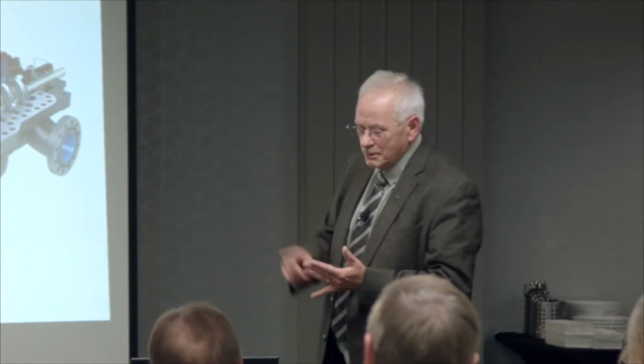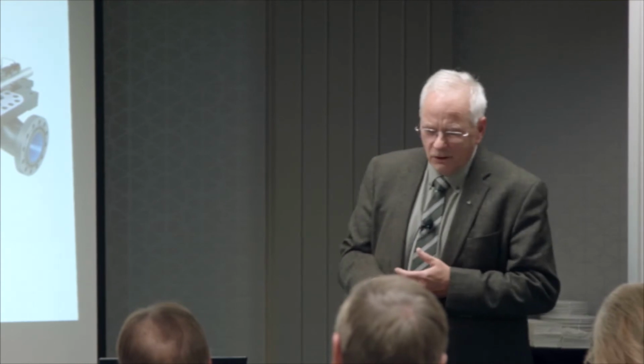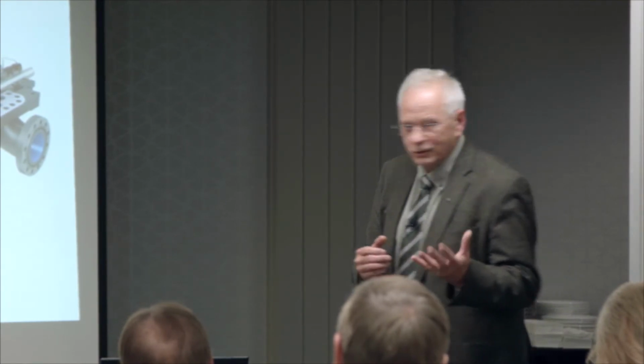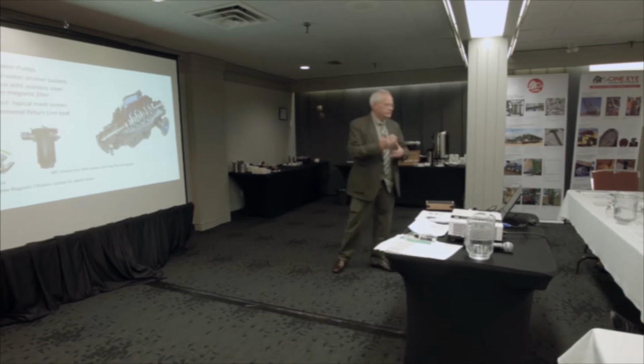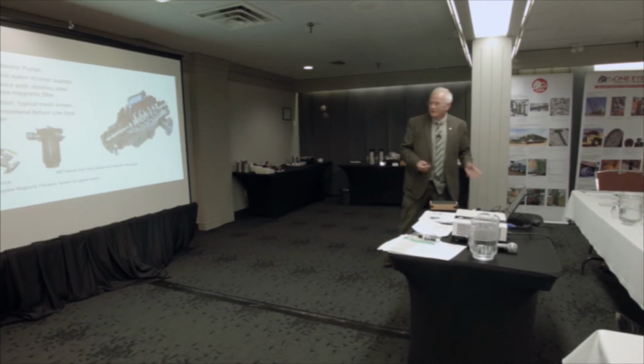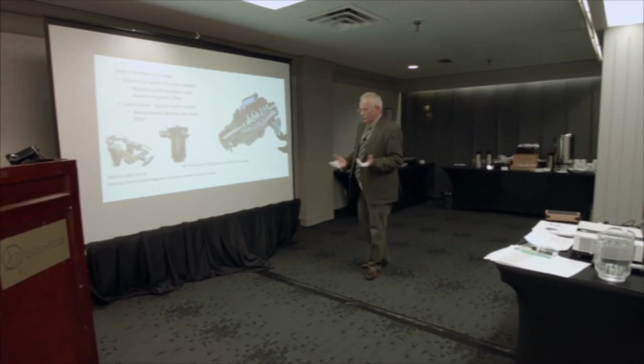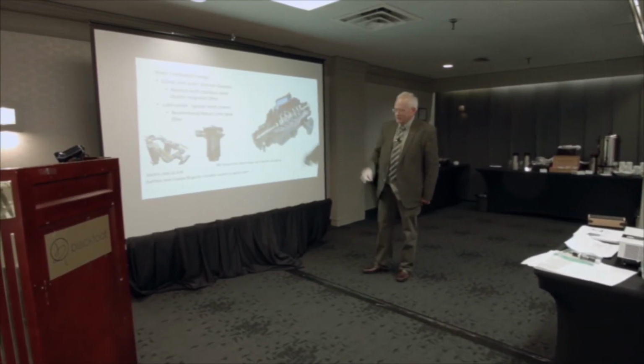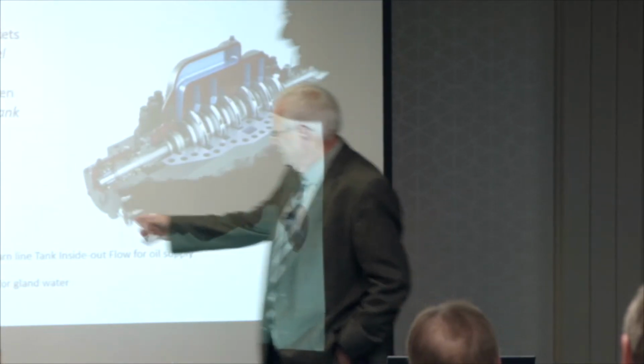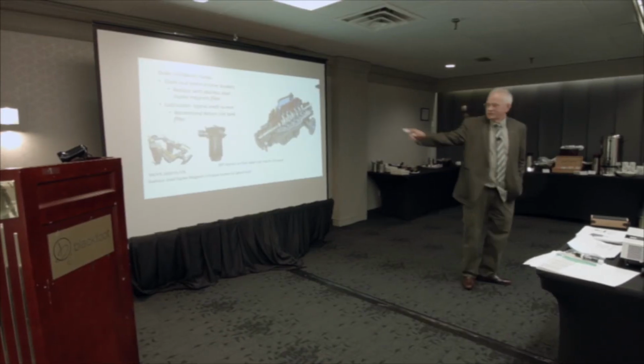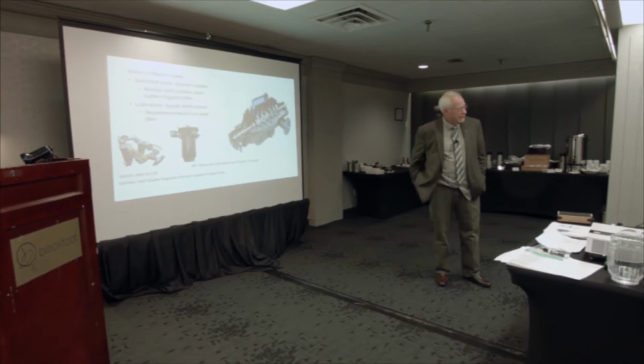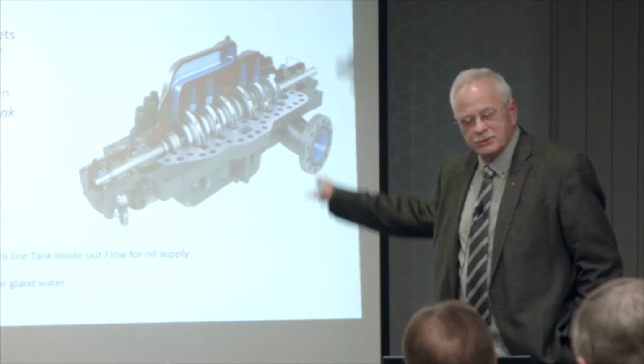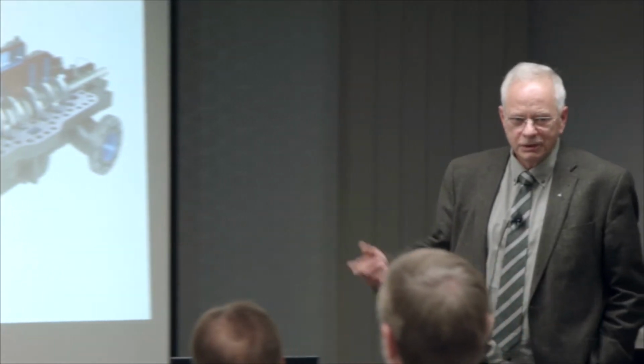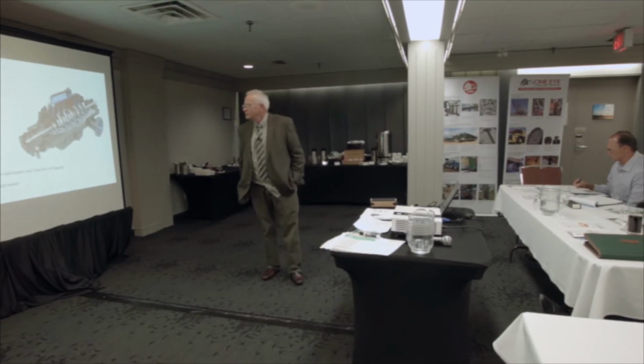Well, being that that's condensate, it's coming off the low temperature, low pressure part of your system, you get a lot of ferrous material, magnetite, spalling off. So these filters were always dirty and plugged, so it's an easy place to put a duplex filter. And again, each one of these feed pumps has a return dump to a tank. So it's easy enough to put a filter in your returns to your tank. The oil supply is driven off a shaft-driven pump, so you could supply it there, but this is probably the easiest place, right in the returns to your tank.